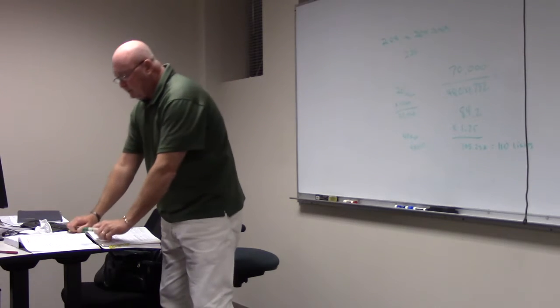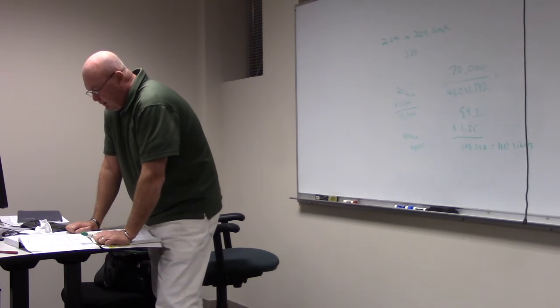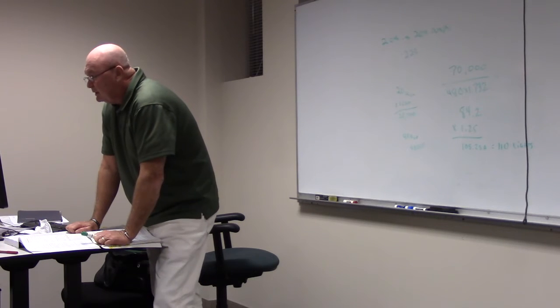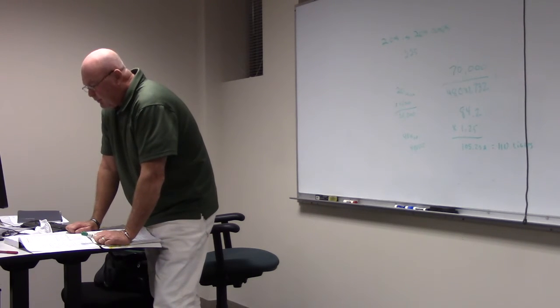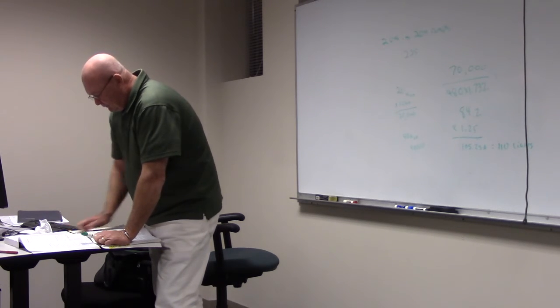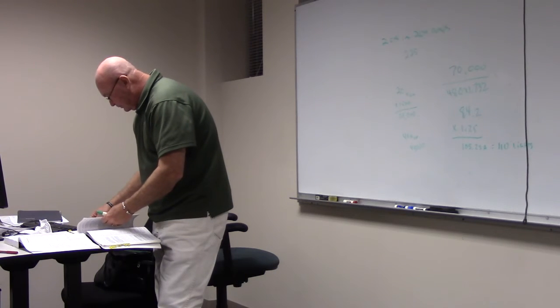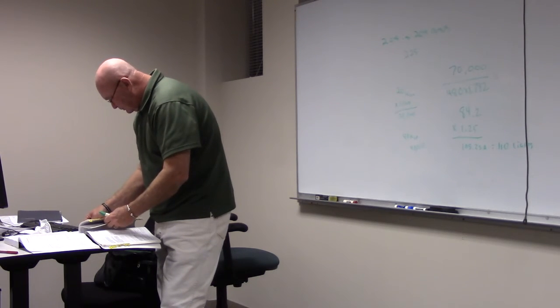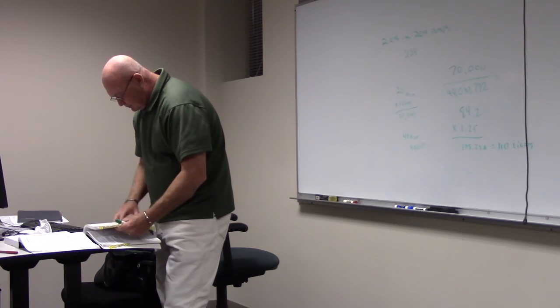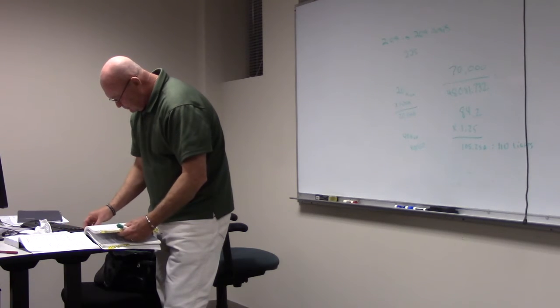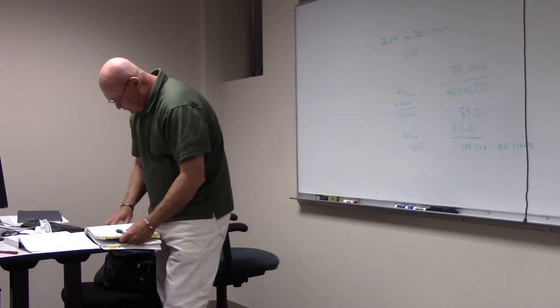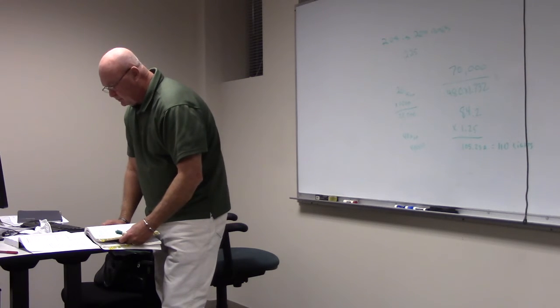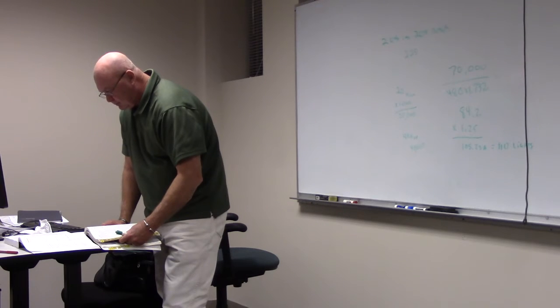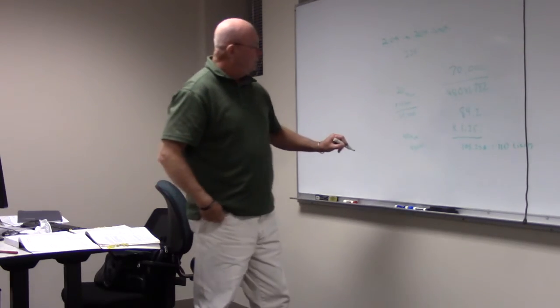Now look at the next part. It requires that motor loads be computed at full load amps. We'd go to our table and we would see the full load amps taken from Table 430.250 for a 3-phase motor, 7.5 horsepower. Let's see what that is. For 460 volts, that's 11 amps.